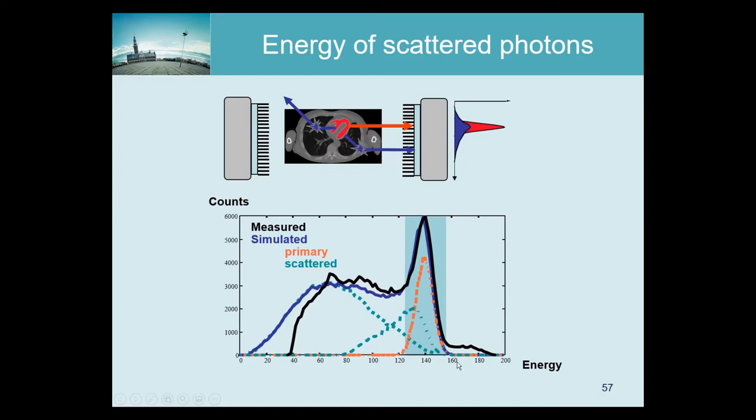Now we can ask the Monte Carlo simulation, just show us the spectrum of the primary photons, only the ones that didn't interact in the patient, and that's this orange line here. And then these are the scattered contributions. So this line here is the energy distribution, the measured energy distribution, of the photons that scattered once in the patient, and this line is the contribution of photons that scattered more than once in the patient. So we see that, yeah, and then we acquire photons within this energy window, and the aim of that energy window is to get as many trues as possible, as many primary photons as possible, and to reject as many scattered photons as possible.